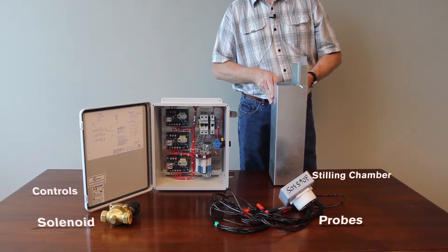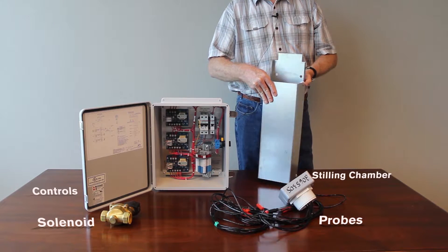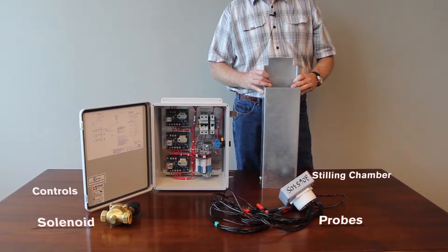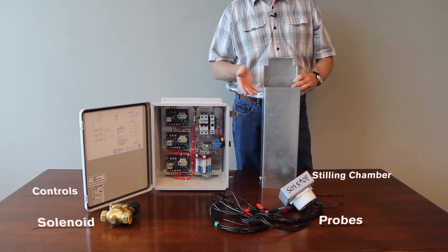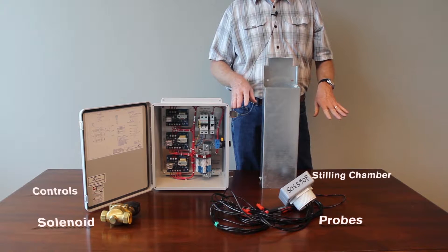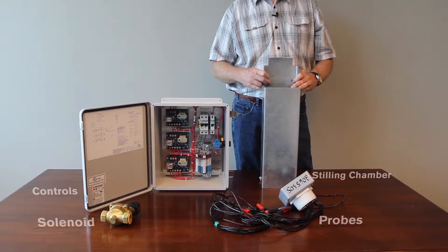As you'll notice it's just a square chamber with an open bottom. The stilling chamber sits off the floor about an inch so mud doesn't clog it up and it has two primary purposes like we said before: to hold the level probes and also to calm the water that might be on the outside. The water inside this chamber is calmer so you get more accurate readings.